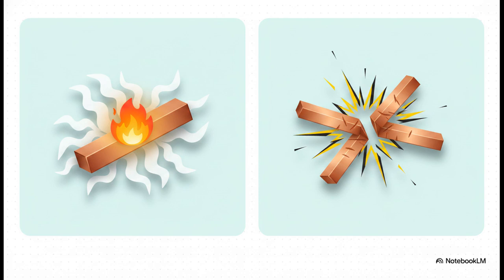First up is the thermal withstand, or ICW. Think of this as runaway, invisible heat, the adiabatic I²T energy that rapidly heats the bar during that split-second clearing time before the breaker trips. Second, we have the dynamic withstand, or IPK. And this isn't about heat at all. It's about sheer physical violence. We're talking about peak magnetic Lorentz forces between parallel conductors that physically push, pull, and literally try to tear the conductors and their supports apart during the very first current peak.